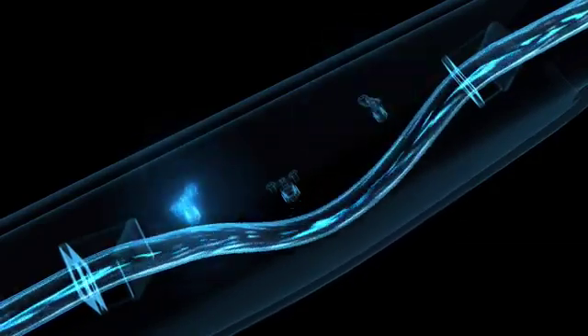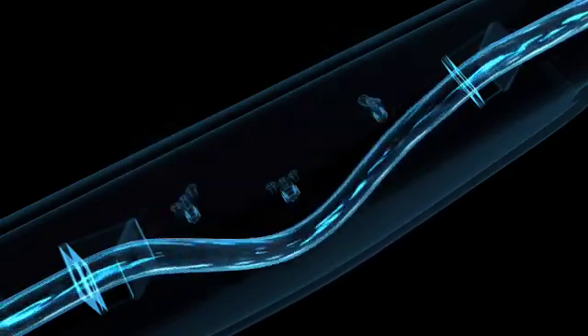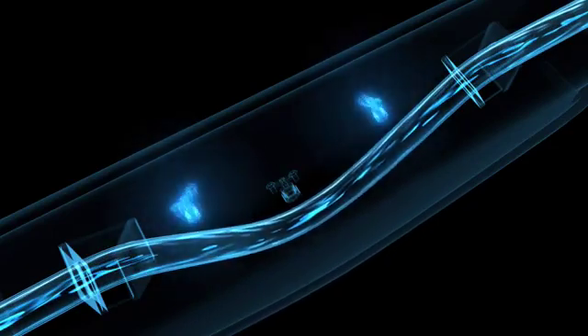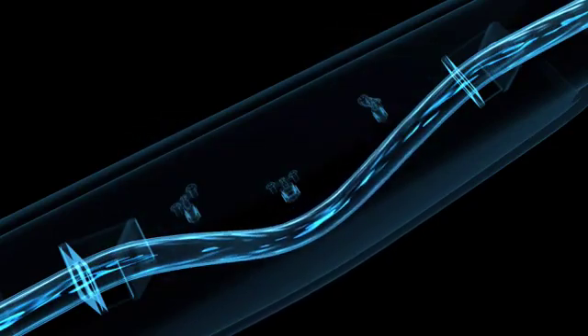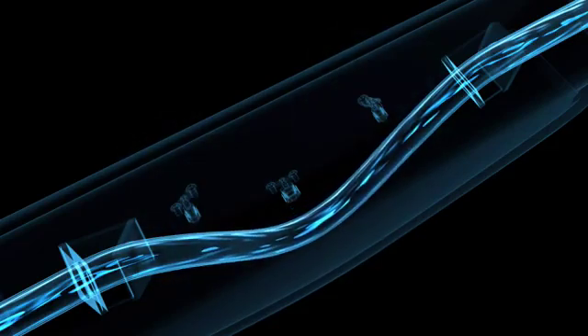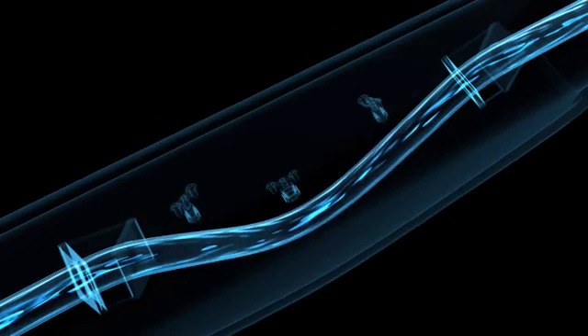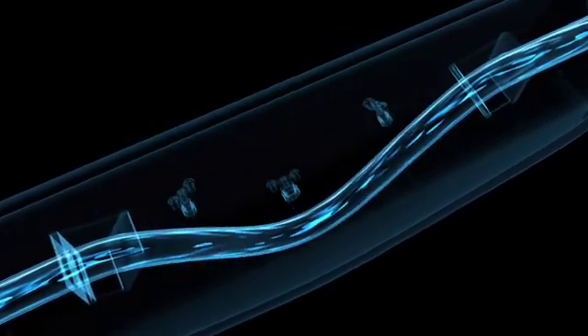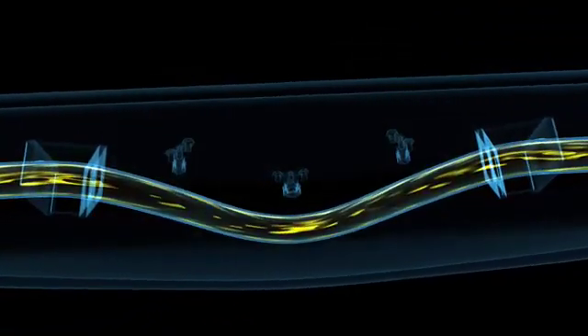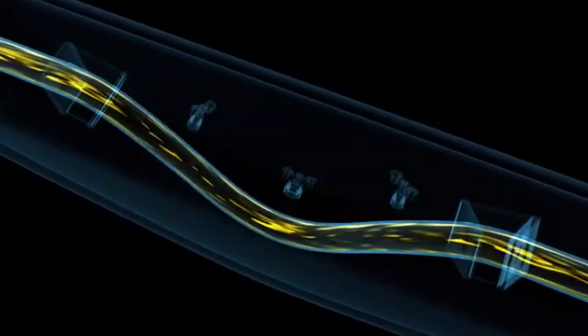The application of the Coriolis measuring principle doesn't stop here. It can also be used to simultaneously determine the density of the flowing fluid. To do so, the sensors also register the oscillating frequency. In other words, how often the measuring tube moves back and forth in one second. From the animation, it's clear that a tube filled with water oscillates more frequently than a tube filled with honey, for example, which has a far higher density.